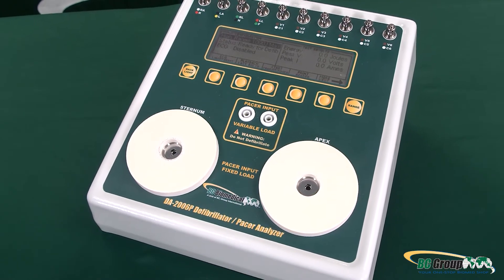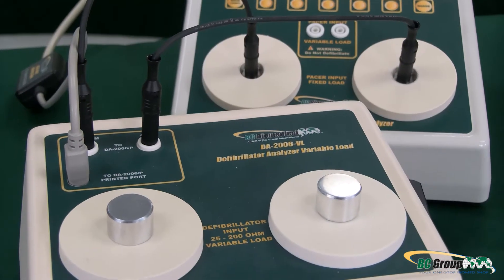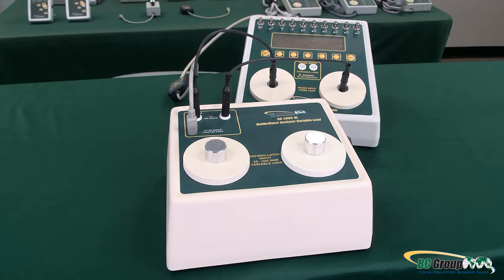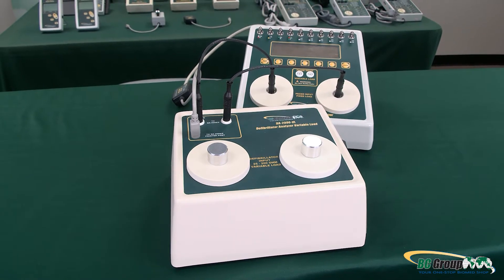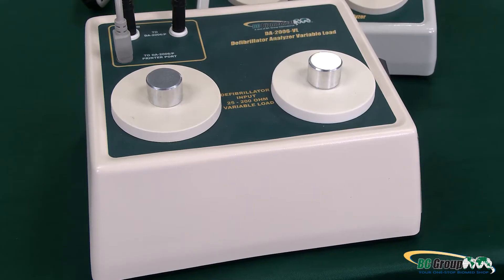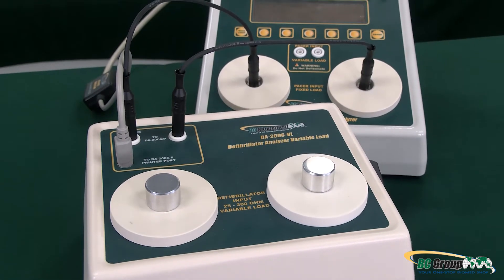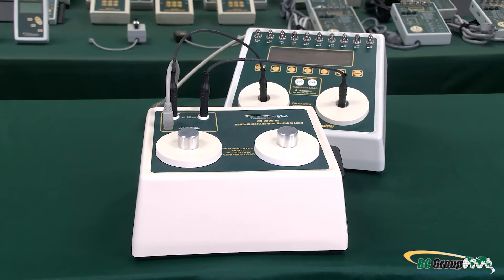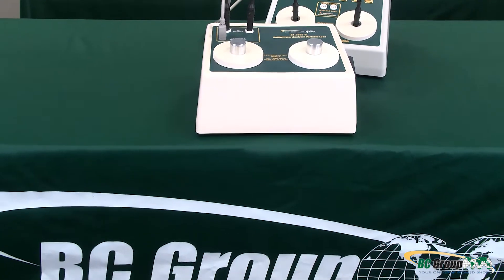The DA-2006 variable load module works easily with the DA-2006 series defibrillator analyzers and provides variable loads from 25 to 200 ohms in 25 ohm steps. When the DA-2006 VL is used with a defibrillator tester, it assures the proper electrical current is delivered to the heart — including all ranges from infant to large adult — per AAMI DF80 and IEC 60601-2-4 standards.